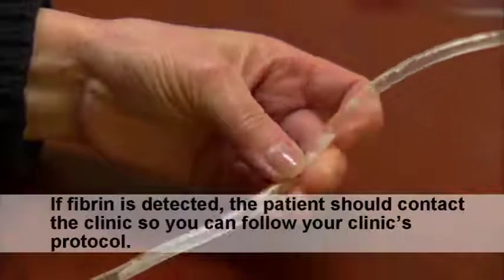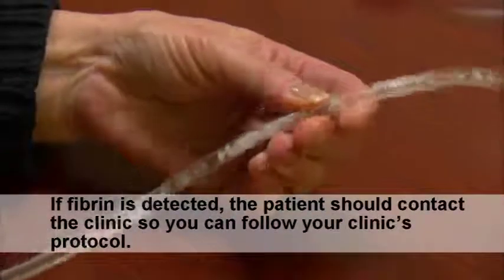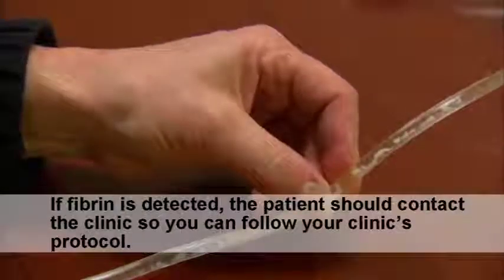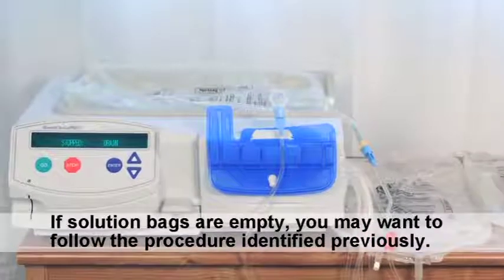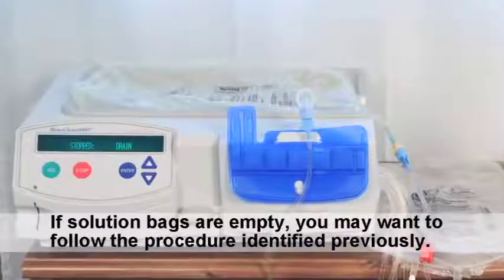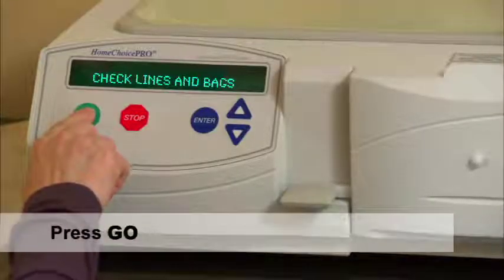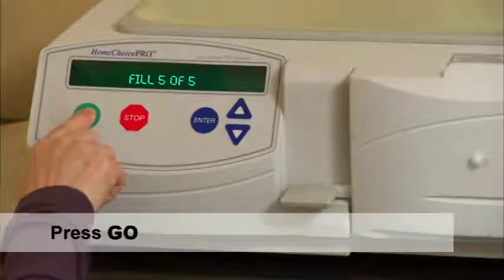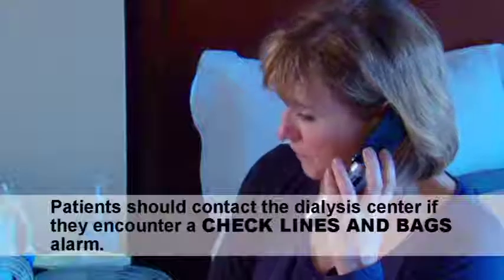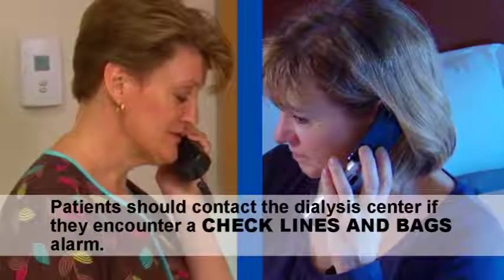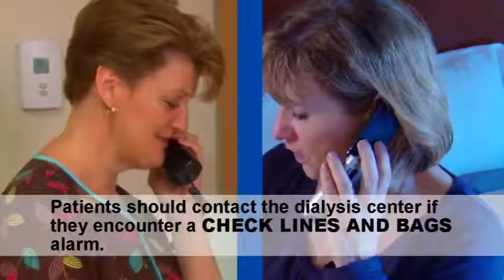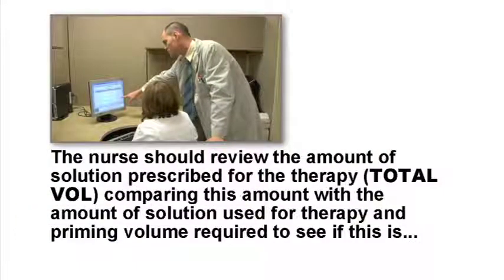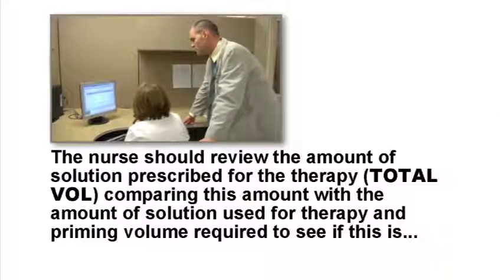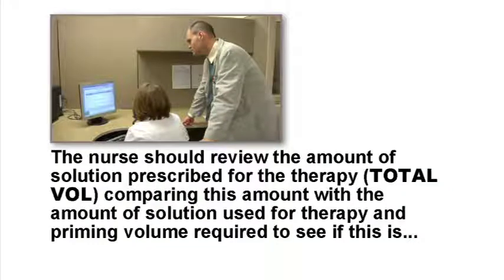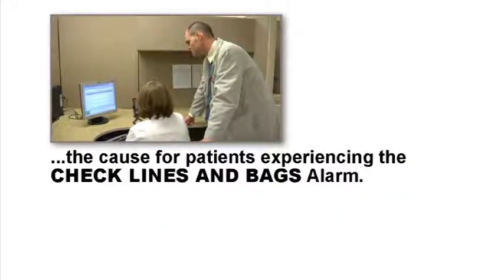If fibrin is detected, the patient should contact the clinic so you can follow your clinic's protocol. If solution bags are empty, you may want to follow the procedure identified previously. When the issue has been resolved, press go and the patient will return to their therapy. Patients should contact the dialysis center if they encounter a check lines and bags alarm. The nurse should review the amount of solution prescribed for the therapy, total volume, comparing this amount with the amount of solution used for therapy and priming volume required to see if this is the cause for patients experiencing the check lines and bags alarm.